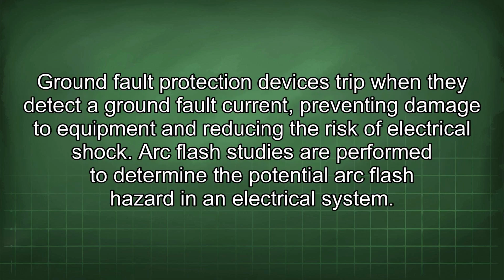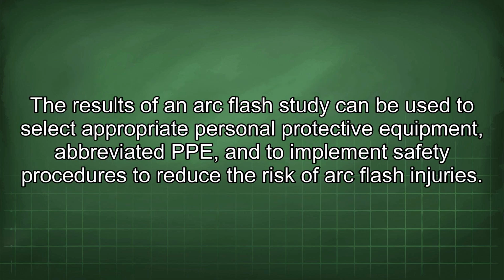Ground fault protection devices trip when they detect a ground fault current, preventing damage to equipment and reducing the risk of electrical shock. Arc flash studies are performed to determine the potential arc flash hazard in an electrical system. The results of an arc flash study can be used to select appropriate personal protective equipment, abbreviated PPE, and to implement safety procedures to reduce the risk of arc flash injuries.